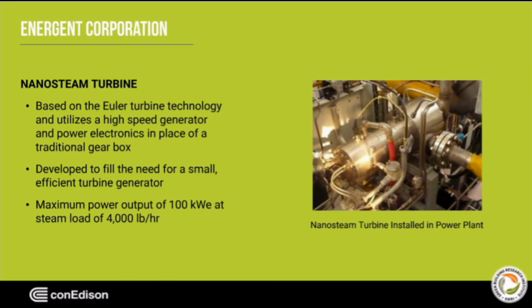The nano steam turbine is similar to the micro steam turbine in that it also utilizes the Euler turbine technology. However, this design utilizes a high-speed generator and power electronics in place of a traditional gearbox. The nano steam turbine was also designed to meet a larger customer market, since it is able to accept smaller steam loads ranging from 1,000 to 4,000 pounds per hour. The maximum electric output of 100 kW is produced with a customer steam load of 4,000 pounds per hour.